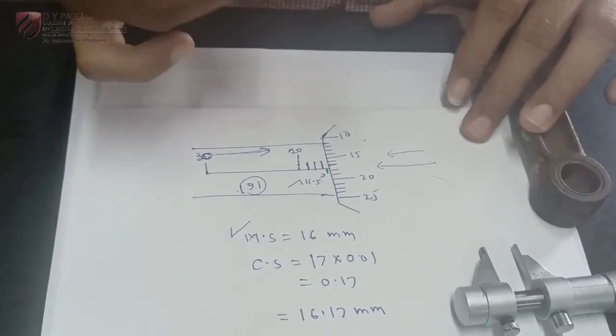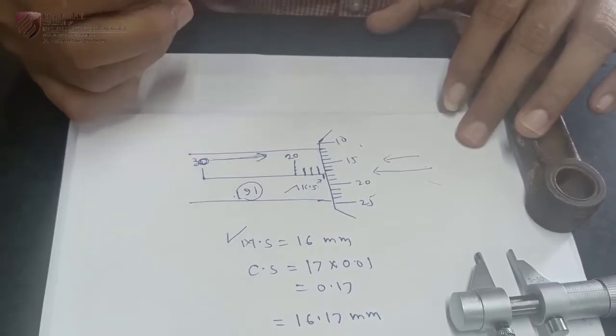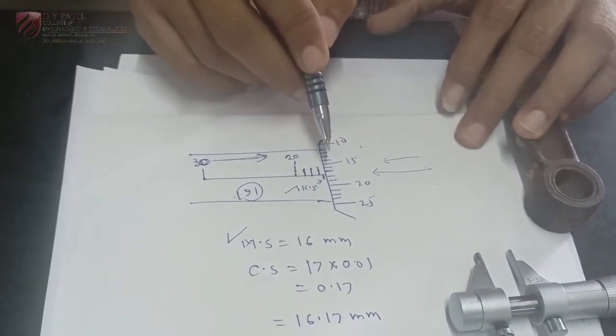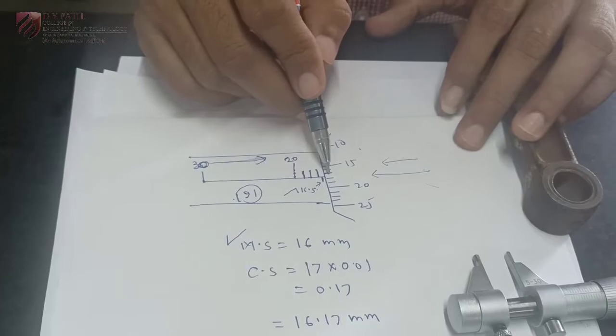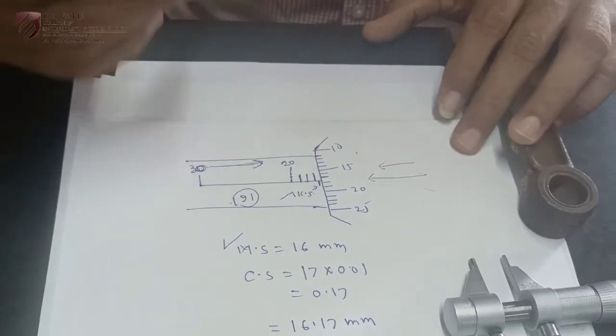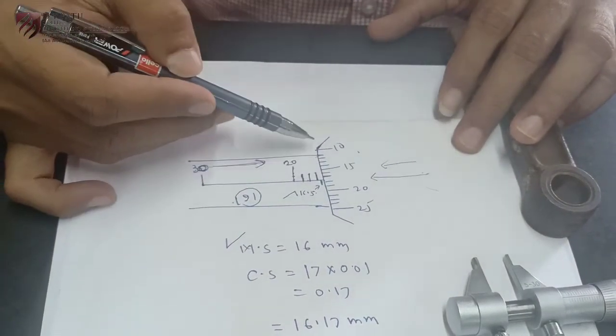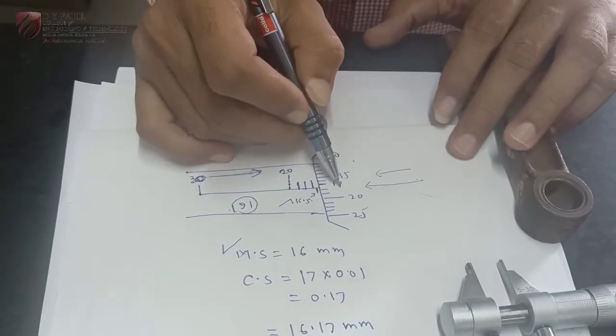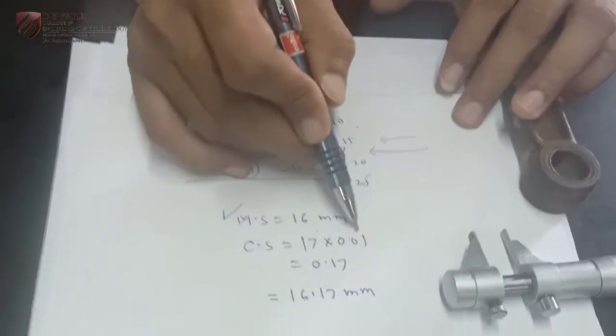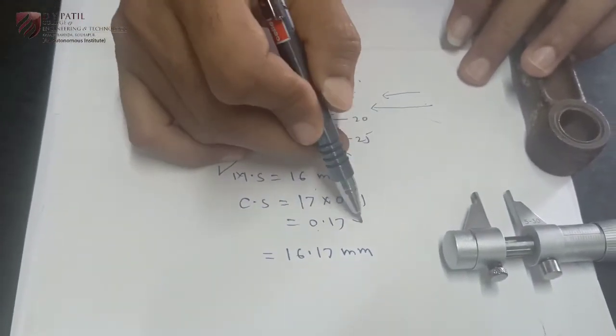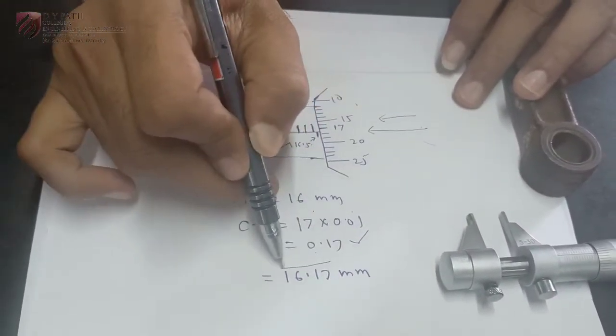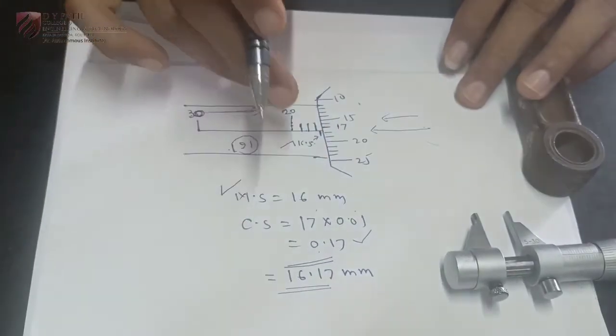To read circular scale, again circular scale is graduated in opposite way. So you have to either find out a match between baseline and circular scale reading or you have to read that reading which is above the baseline. For example here the reading which is above is division number 17. So 17 multiplied by 0.01 is the least count, 0.17 is the reading. So 16.17mm is the final reading of this inside micrometer.